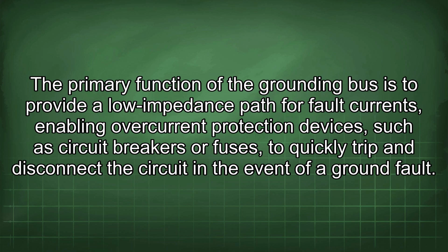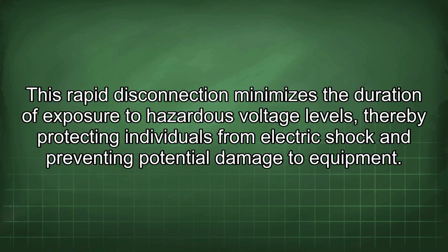The primary function of the grounding bus is to provide a low impedance path for fault currents, enabling overcurrent protection devices such as circuit breakers or fuses to quickly trip and disconnect the circuit in the event of a ground fault. This rapid disconnection minimizes the duration of exposure to hazardous voltage levels, thereby protecting individuals from electric shock and preventing potential damage to equipment.